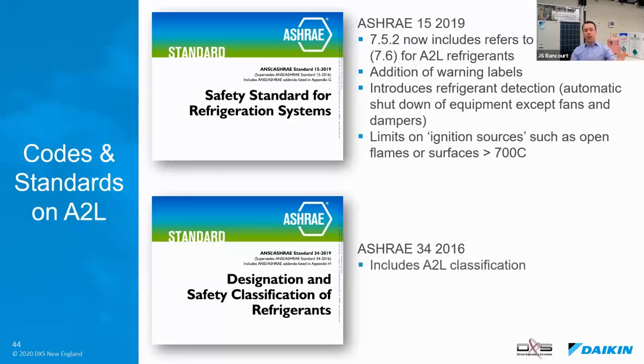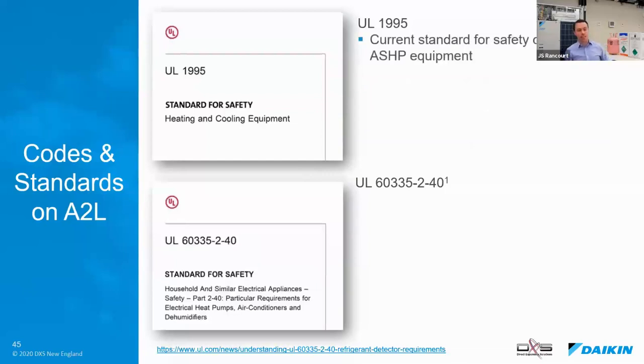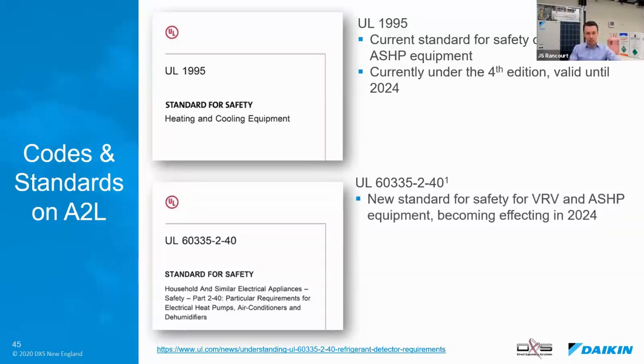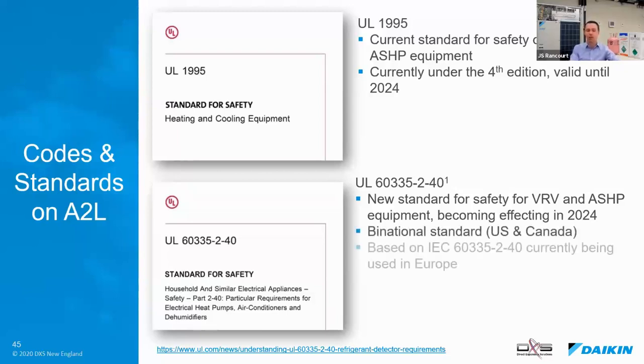ASHRAE 34 also, as I showed earlier, now has the A2L classification in there, which R32 falls under. How about equipment standards? Right now, all of our equipment is tested under UL 1995, and that is going to be valid until 2024. Although what's currently in the pipeline is UL 60335-2-40. Don't ask me why it's named that way, but this is the new standard for VRV and air source heat pump, becoming effective in 2024. It's a binational code. US and Canada will follow the same code. It's based on the international code, which is currently being used in Europe, which is why Europe can use A2Ls in buildings, which is why Europe already has phased down the F-gas regulations. They already have phase downs on HFCs.